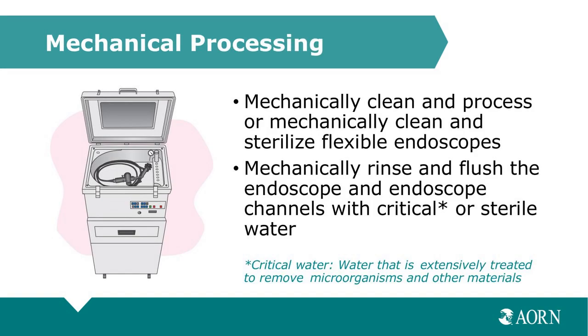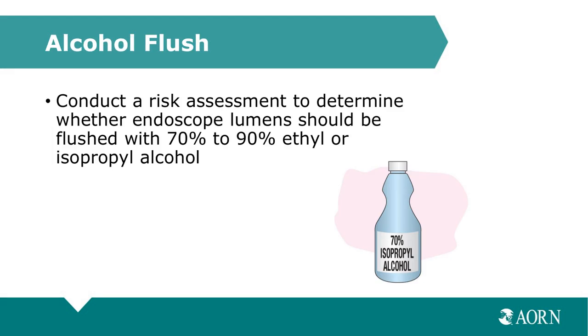in the disinfection process. Now, following disinfection or liquid chemical sterilization, the endoscope and its channel should be mechanically rinsed and flushed with either critical or sterile water. We recommend that a multidisciplinary team conduct a risk assessment to determine whether your endoscope lumen should be flushed with 70 to 90% ethyl or isopropyl alcohol.